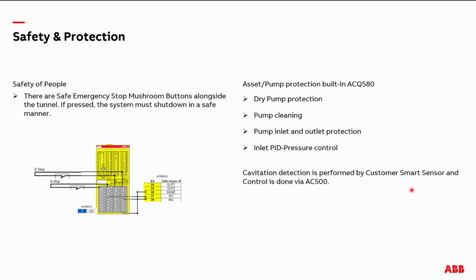There are also application notes you can find on how we can run the AC500 safety protocols via 5G, for example. And no matter where this emergency stop button is pressed, the complete tunneling system, these 500 tons of material which is moving, is brought down safely to a stop status, and then the STO is switched on the frequency converters, where the pumps are then in a safe torque off mode.